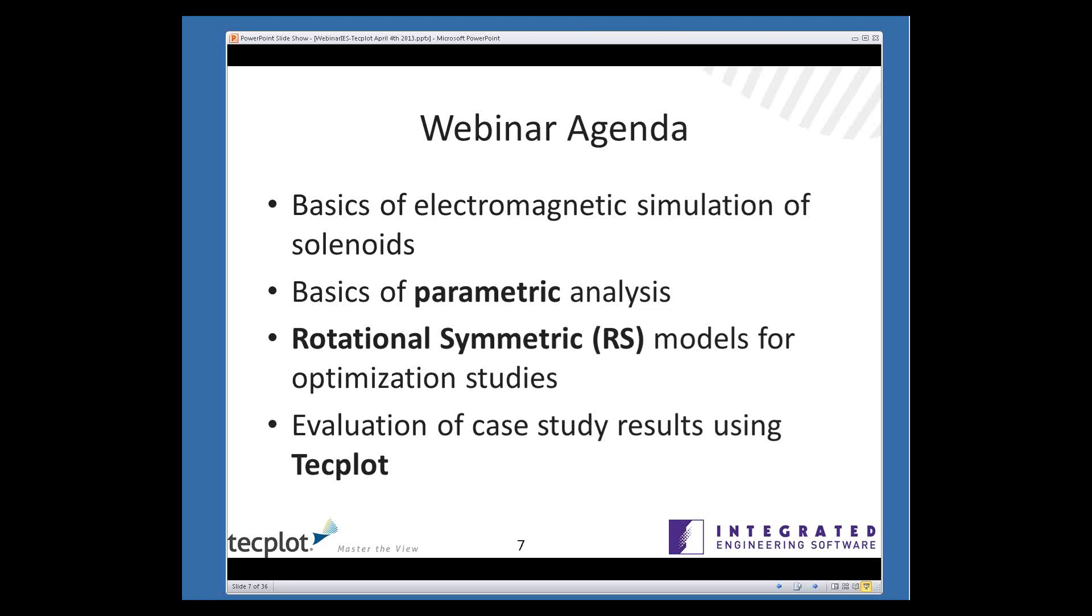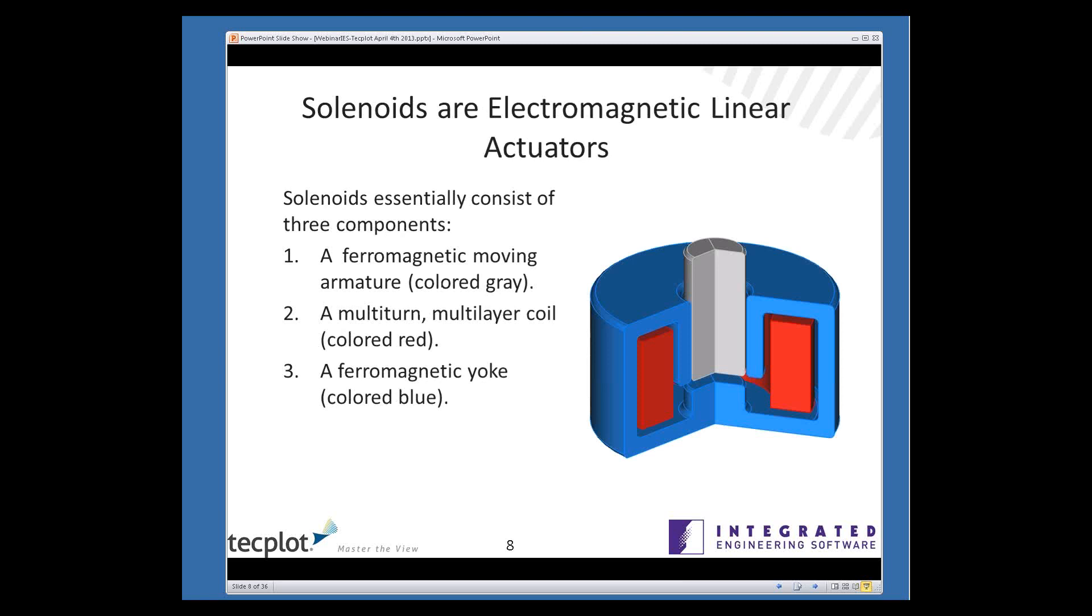When people talk about solenoids, usually they're referring to linear electromagnetic actuators, as I'm showing here. You can boil them down to three basic components. There's some sort of a moving armature, a core or plunger, which we colored gray in the picture. There's an electrical coil, a multilayer turn coil, which provides the magnetization. And then a ferromagnetic yoke or case, which we colored blue, and that provides the complete magnetic path.